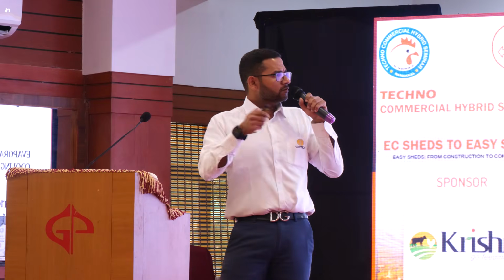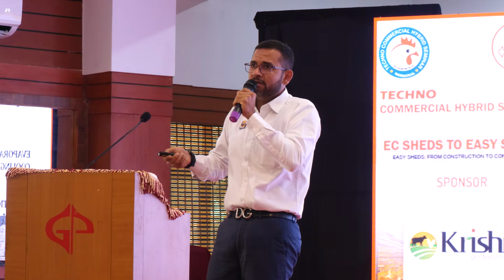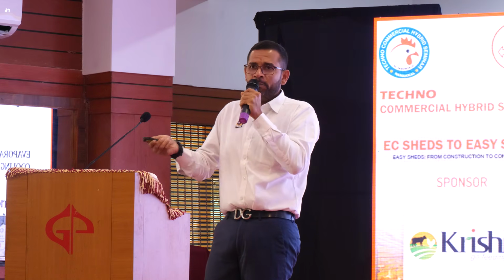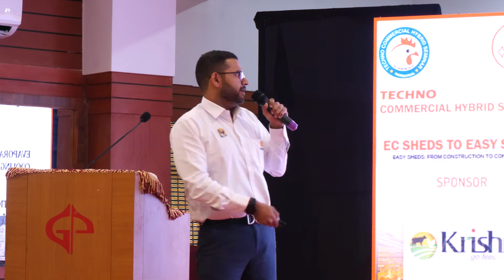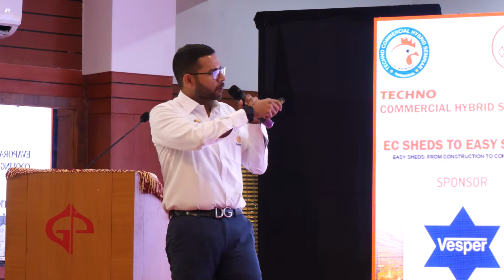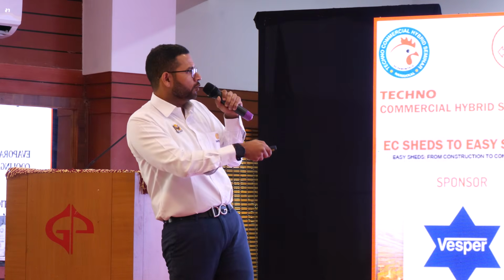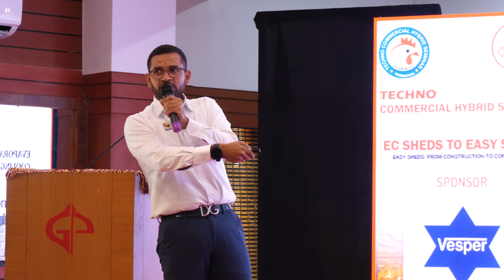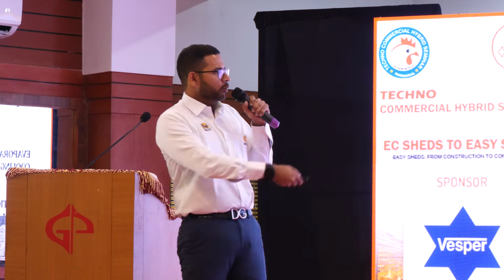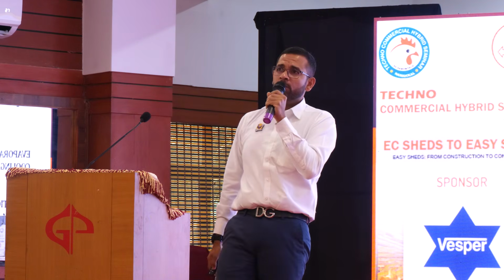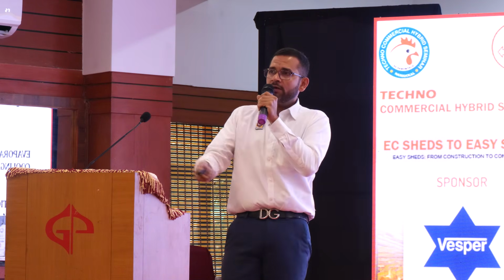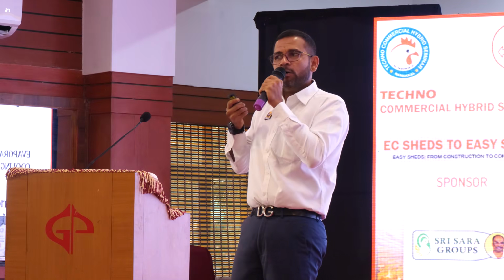So what is the solution? If you don't want to do all of this, we can put an AC in the house, but AC is not practical. This is a simple chart. I will not go through all the details, but just to let you know, for a 50,000-bird commercial layer house, if you put an AC, you will end up spending around 22,000 rupees per hour to get what you need inside the house. Thus, AC is something that is not practical.